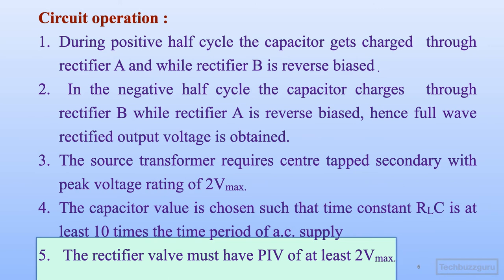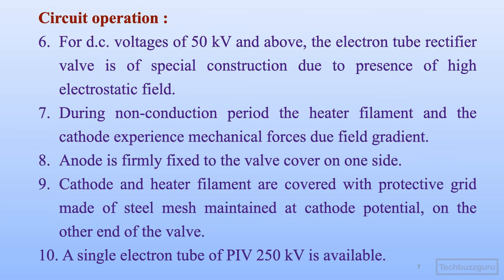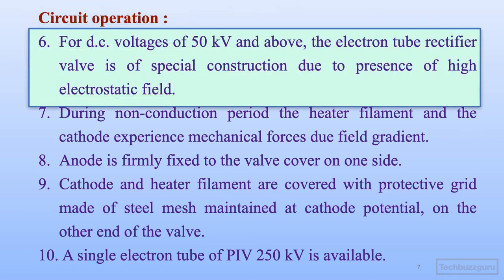Each rectifier valve must have a peak inverse voltage (PIV) of at least twice Vmax — this is the voltage that appears across an individual rectifier when it is in the reverse bias condition. These circuit details are common features of high voltage rectifier circuits, also covered during the half wave rectifier discussion. For DC voltages of 50 kV and higher, electron tube rectifier valves have special construction due to the high electrostatic field.